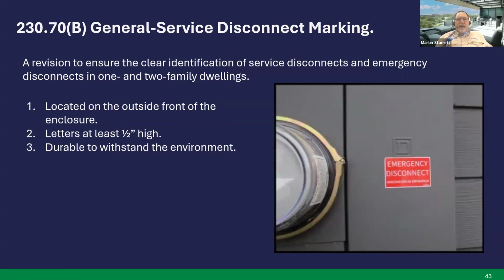Okay, so 230.70(B), service disconnect marking, a revision to ensure the clear identification of service disconnects and emergency disconnects in one and two family dwellings. This same language is in 225.41 as well. It's got to be located on the outside front of the enclosure, and I hope everybody sees this right here. And if nobody's in this webinar, I'd like for everybody to tell other electricians that the letters are going to have to be at least half an inch high. If you've got these emergency disconnect labels, the letters have to be a half inch high, and of course, durable to withstand the environment.